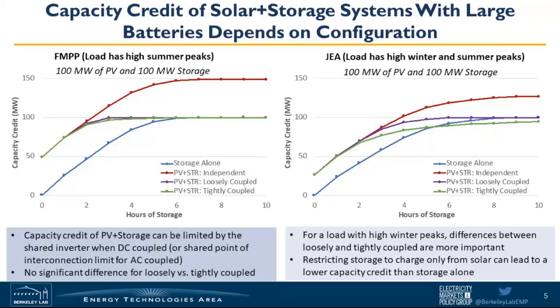Okay, and then if we restrict the battery to charge just from solar in this tightly coupled case, it only really seems to matter for this utility that has high winter peaks on the right-hand side. Here we saw some events where extended cloudy periods during the winter peaks would lessen the ability to charge storage, and that resulted in a capacity credit of this coupled system that could be even lower than for that standalone storage system.